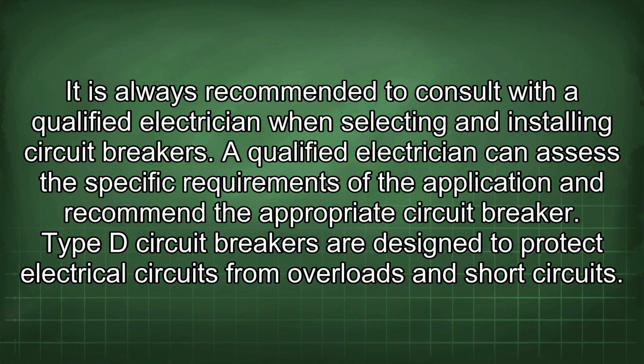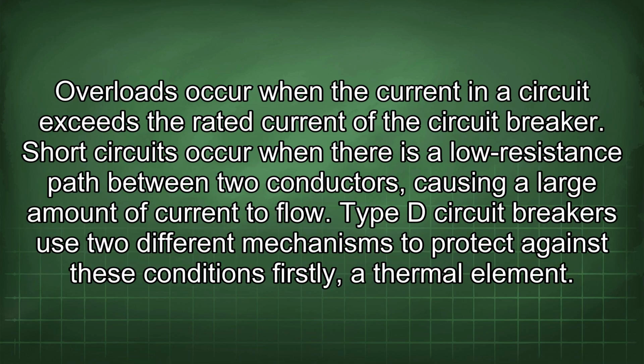Type D circuit breakers are designed to protect electrical circuits from overloads and short circuits. Overloads occur when the current in a circuit exceeds the rated current of the circuit breaker. Short circuits occur when there is a low resistance path between two conductors, causing a large amount of current to flow. Type D circuit breakers use two different mechanisms to protect against these conditions.